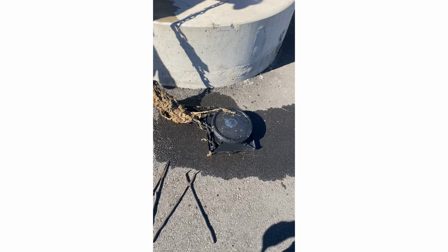So as you can see in that video, we had some pieces of rags, shirts, hair, dental floss, all kinds of stuff that just ends up in the sewer. And it was getting wrapped around the aerator chain that goes down to hold the diffuser in. And like I said in the video, better it gets wrapped around that chain than ends up in the pumps. So we end up cleaning this off once every 3 months while doing station checks, and it keeps the wet well still running nice.